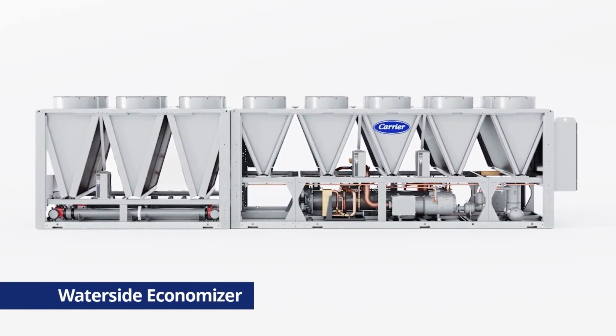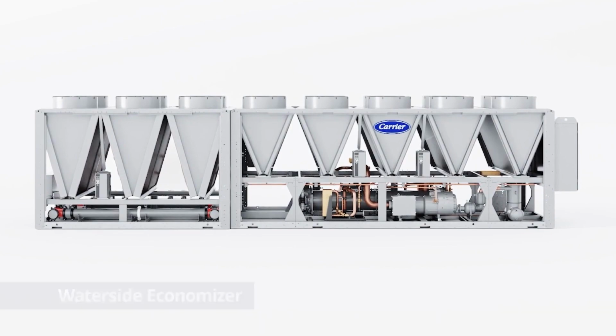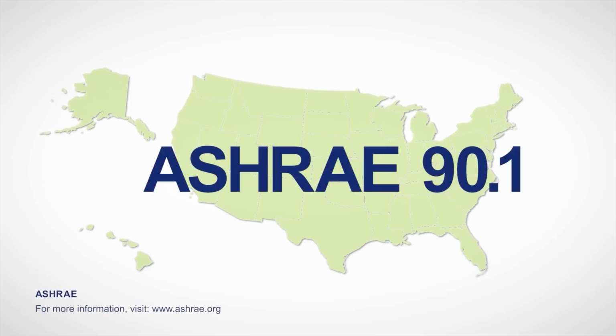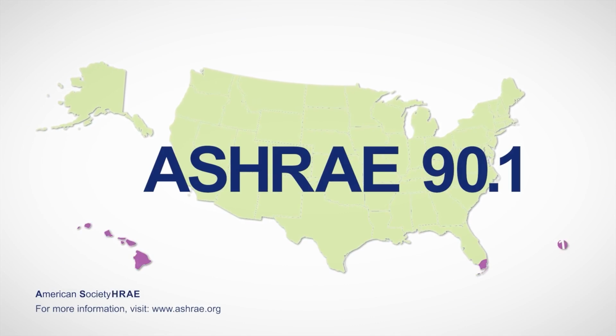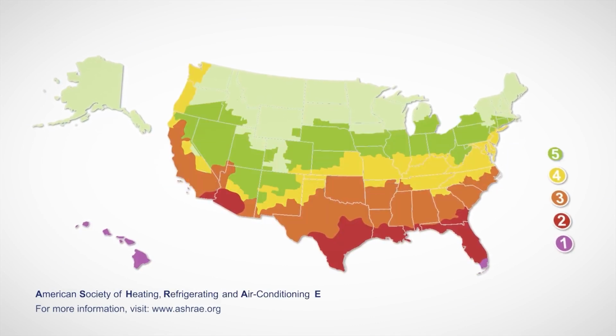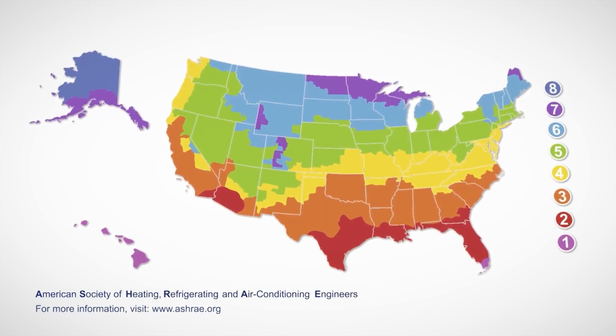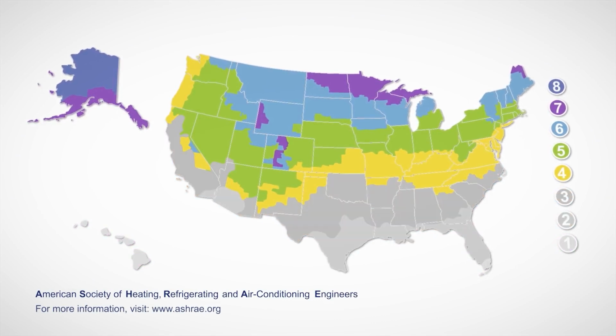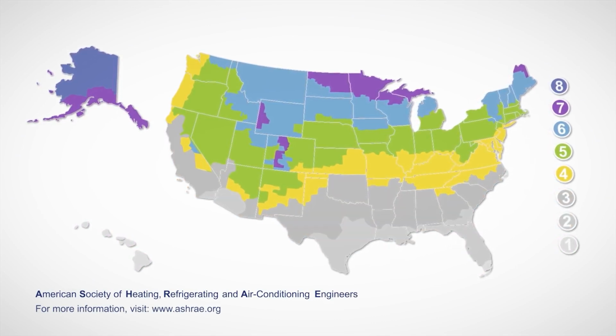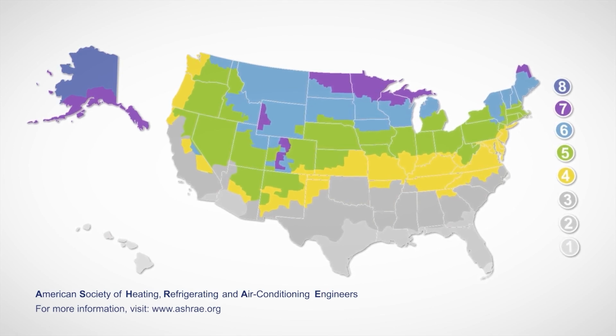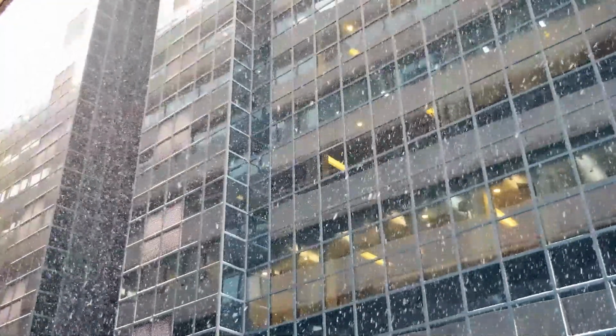There are a few reasons a free cooling system might be used. One is to meet ASHRAE Code 90.1 requirements. ASHRAE breaks the country into different climate zones. Any location in Zone 4 or above needs to have either an air or water-side economizer to meet the code.